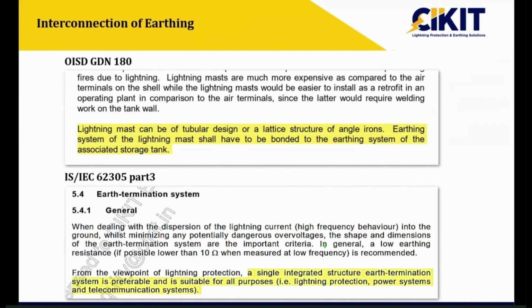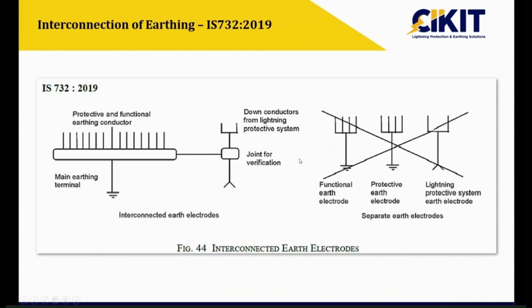So these are the different standards which explain interconnecting the earthing of the lightning protection system with other equipment. The first one is from OISD GDN 180. Here they highlight that lightning mast earthing can be connected with tank earthing. The second one is from 62305. Here also they mention that lightning protection earthing can be linked with the power system earthing. This one is from IS 732. Here also they interconnect the lightning protection system earthing with other earthing.